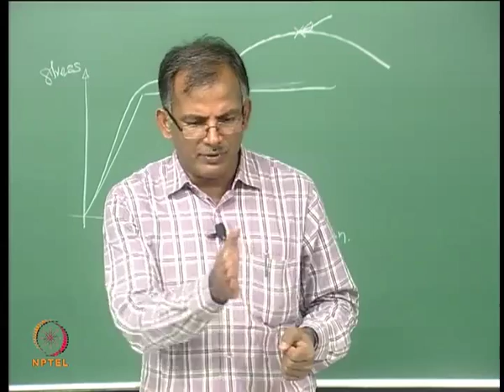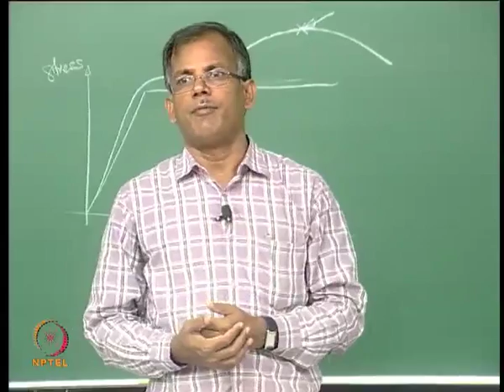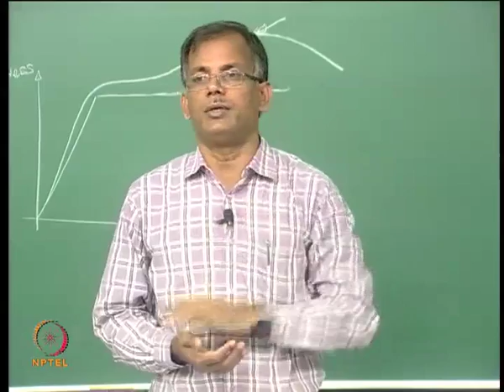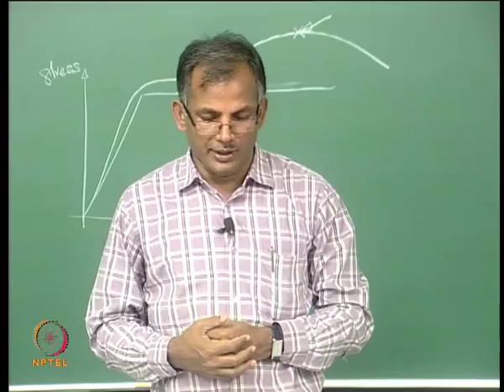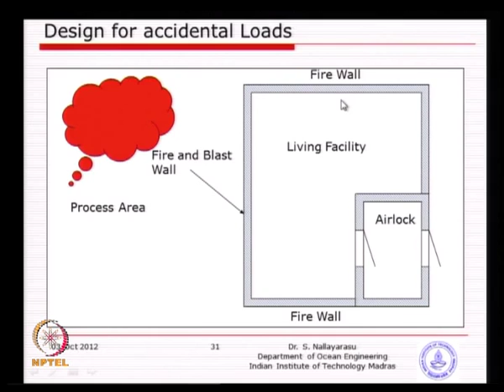And whenever you have this safe area in the vicinity of the process area, you need to make sure of double safety for something like this. You see here, when you enter, you have a double door. So, the first door opens, and hydrocarbon entering into the room is avoided because you have another lock. This is called the airlock, which is nothing but a double door which prevents the entry of any foreign material like hydrocarbon gas, and especially smoke. All the time one of them is closed, and there will be an exhaust from that particular chamber, so that whatever is entering is recycled, and it is surrounded by firewall all around the facility.